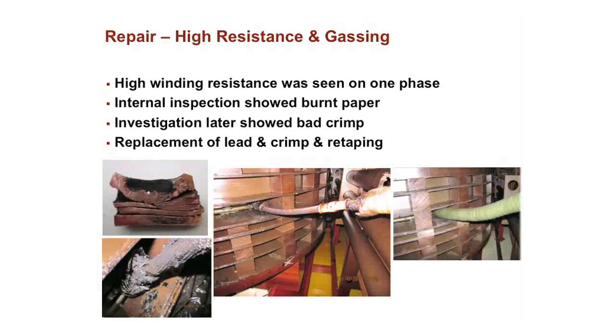So an internal inspection was done, and it found an issue with a lead where a crimp was becoming loose inside of the lead. By untaping that and cleaning everything up, you took away that risk. This was a cutaway view of the crimp. There's supposed to be three cables coming through here, but you can see that the crimp was done such that only one of the three cables ended up going through. So this overheated seriously over time, and eventually it would have burned up, and you could have had a very bad dielectric failure.